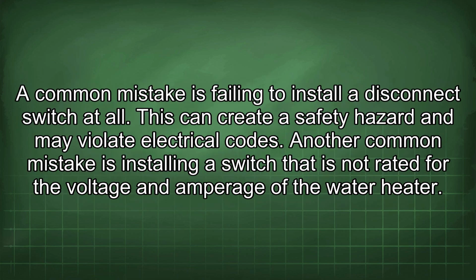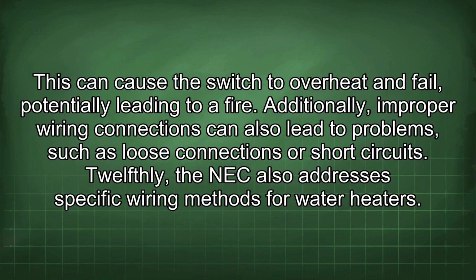A common mistake is failing to install a disconnect switch at all. This can create a safety hazard and may violate electrical codes. Another common mistake is installing a switch that is not rated for the voltage and amperage of the water heater. This can cause the switch to overheat and fail, potentially leading to a fire. Additionally, improper wiring connections can also lead to problems such as loose connections or short circuits. 12thly, the NEC also addresses specific wiring methods for water heaters.